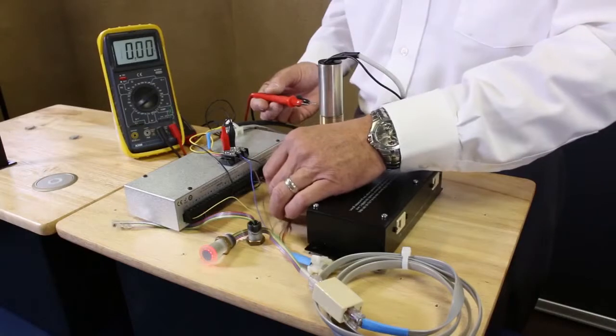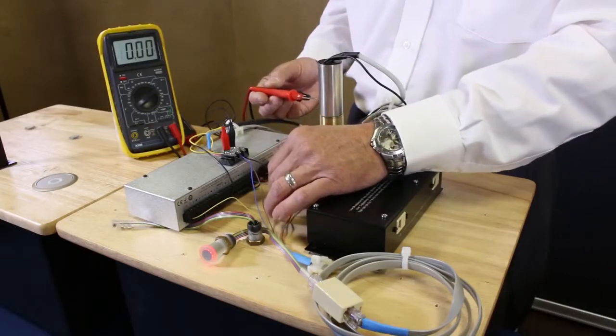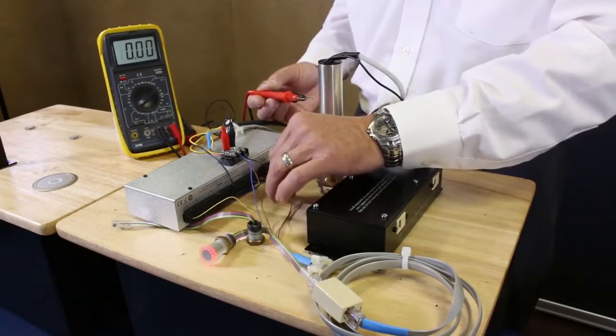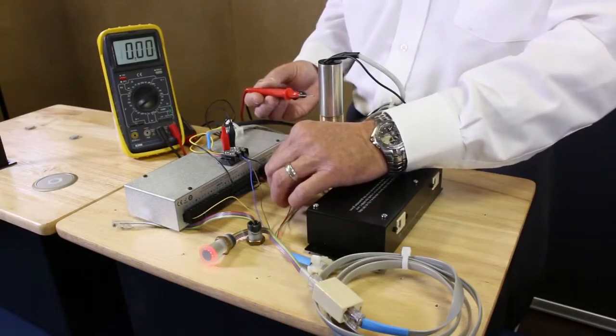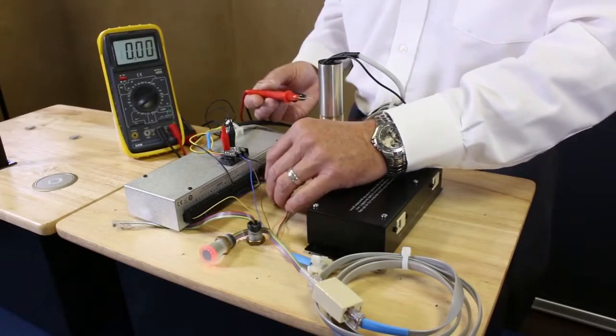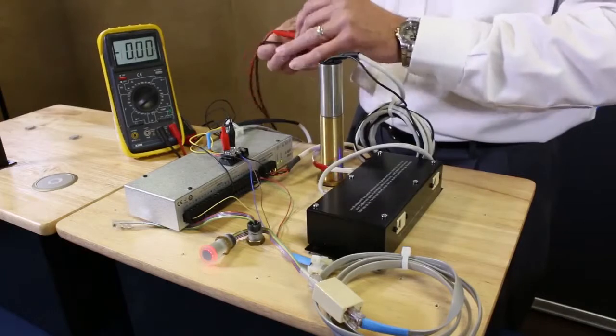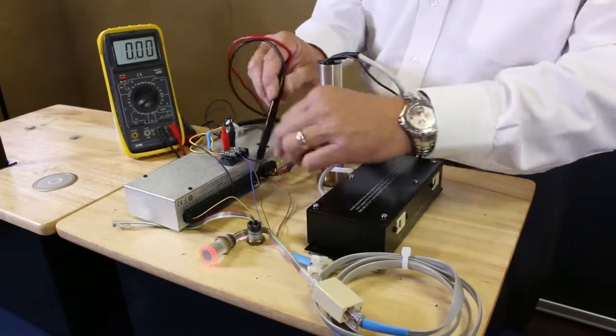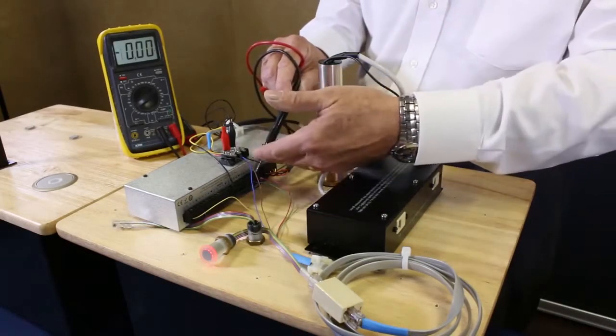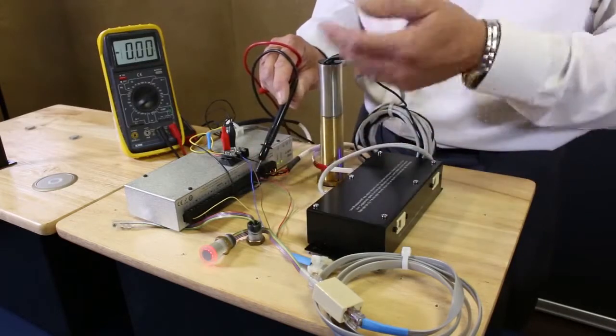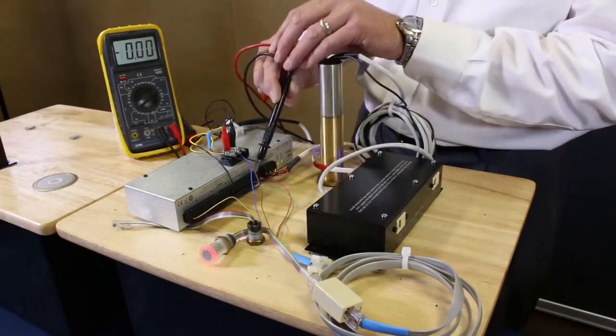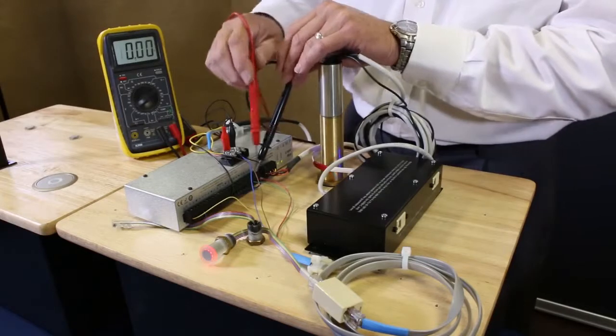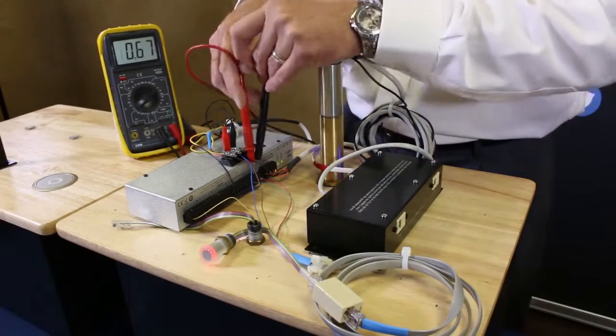It's important to understand that the green wire controls the green LEDs and the red wire controls the red LED ring. So I can come in here and place my probe on the ground, which happens to be on the logic box, the last terminal designated with a ground indicator, and then place the other probe on one of the colors.